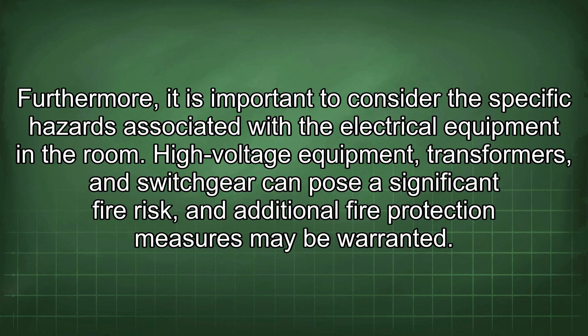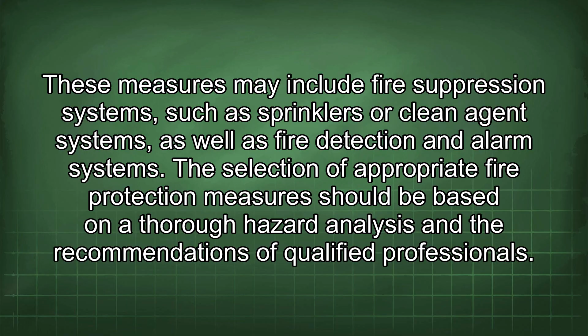Furthermore, it is important to consider the specific hazards associated with the electrical equipment in the room. High-voltage equipment, transformers, and switchgear can pose a significant fire risk, and additional fire protection measures may be warranted. These measures may include fire suppression systems, such as sprinklers or clean agent systems, as well as fire detection and alarm systems. The selection of appropriate fire protection measures should be based on a thorough hazard analysis and the recommendations of qualified professionals.